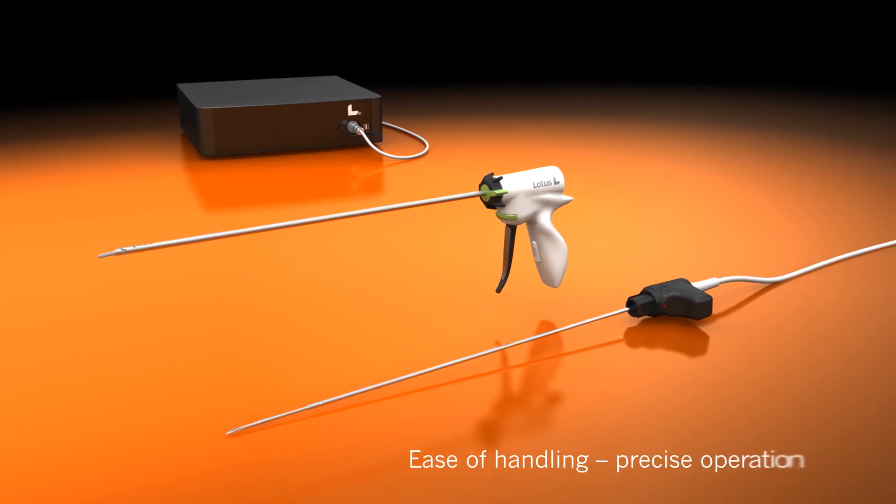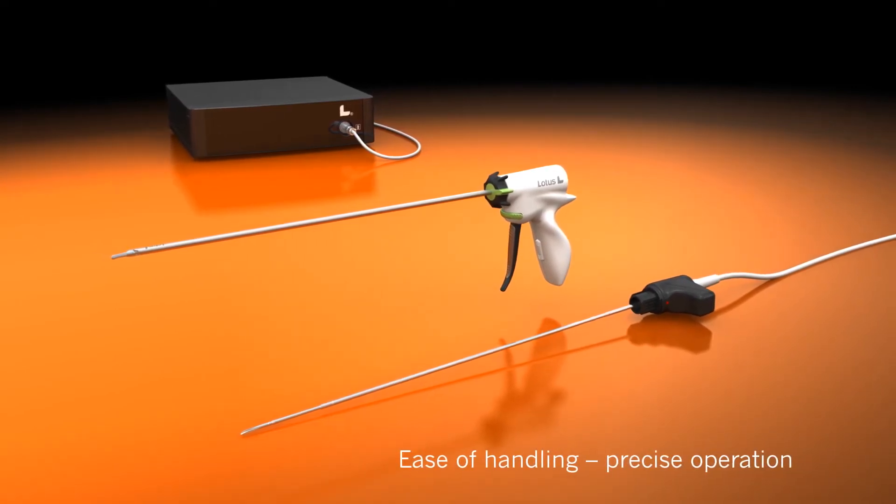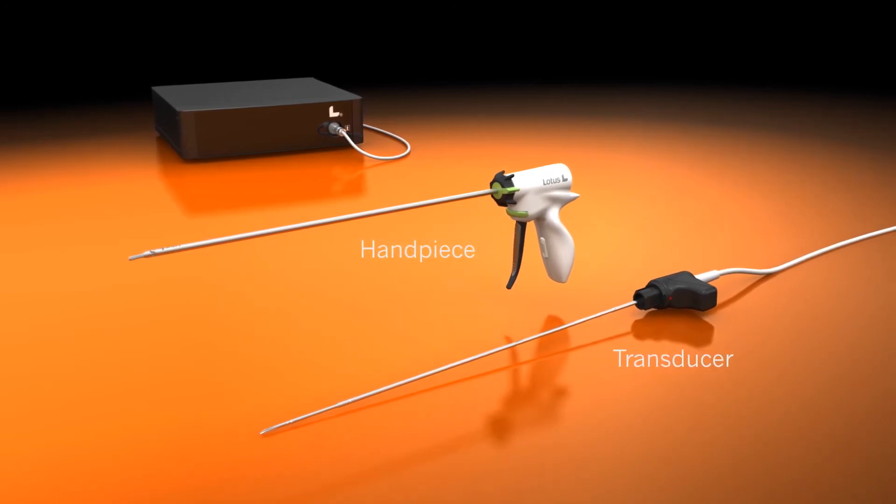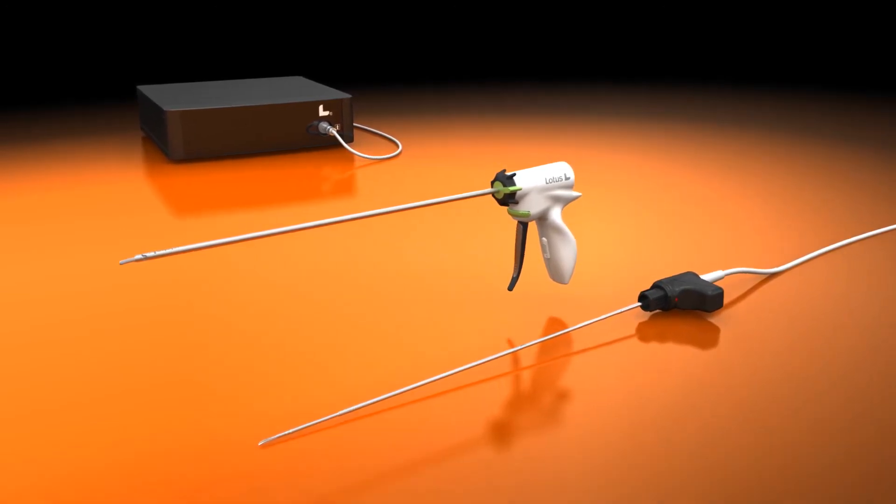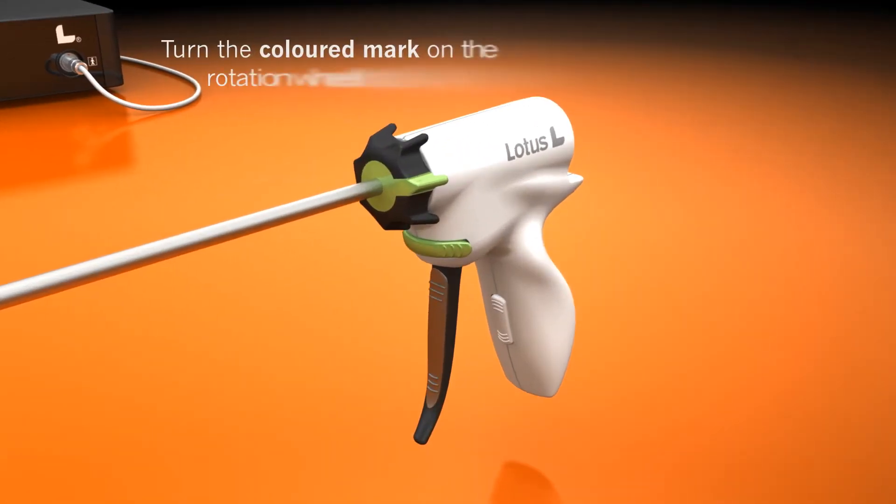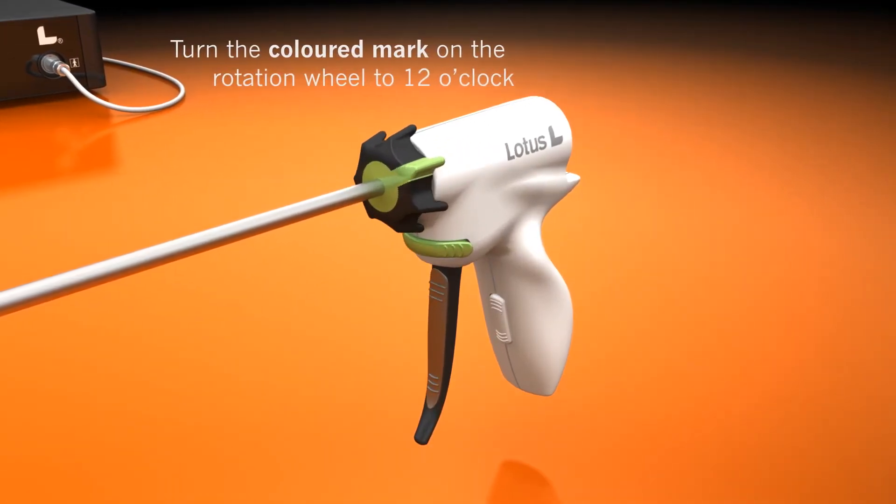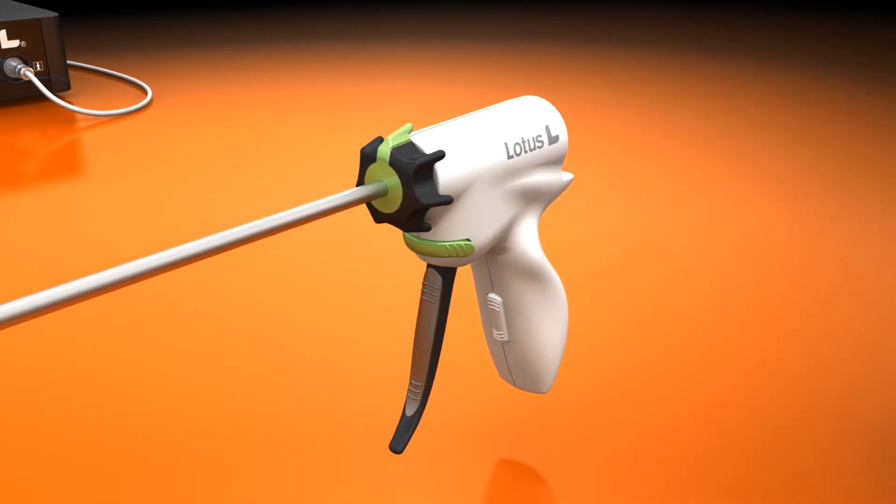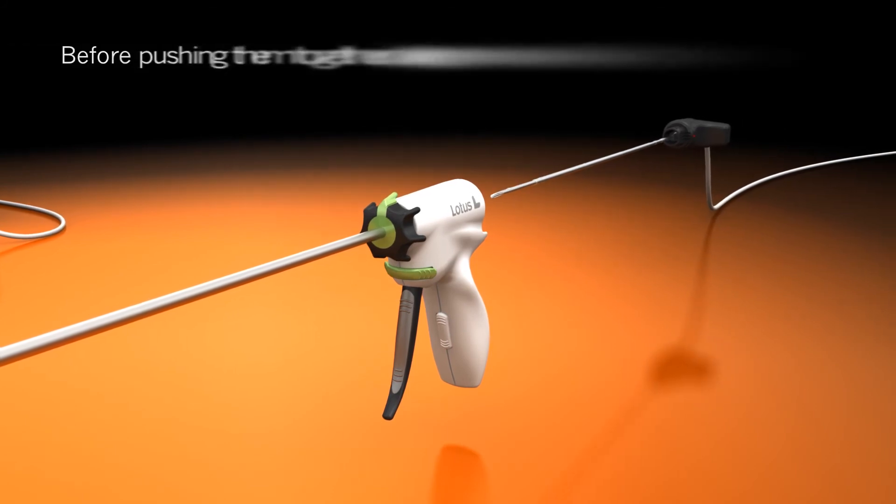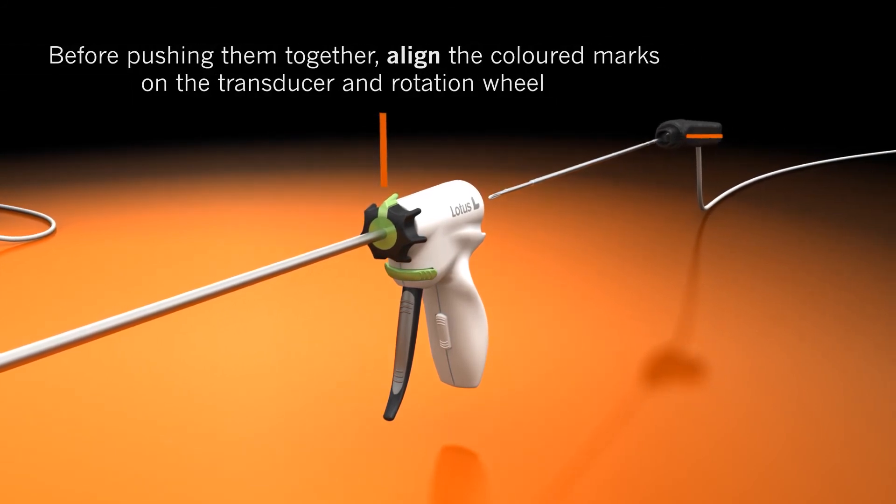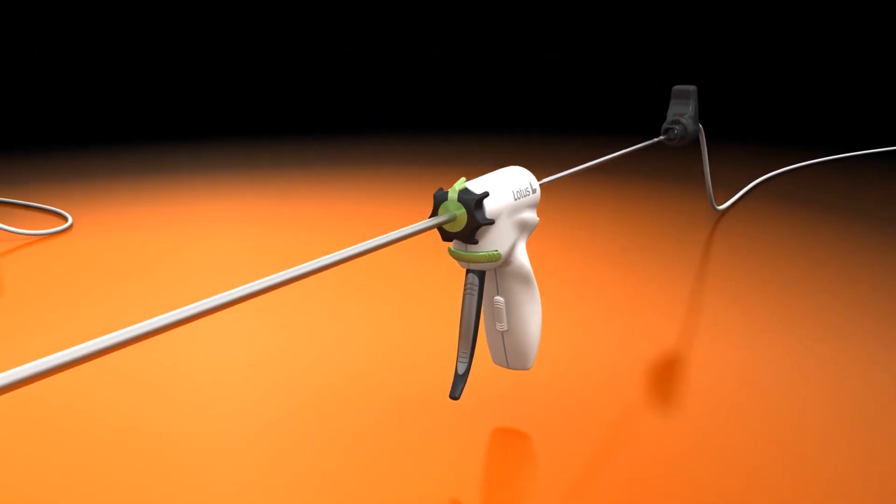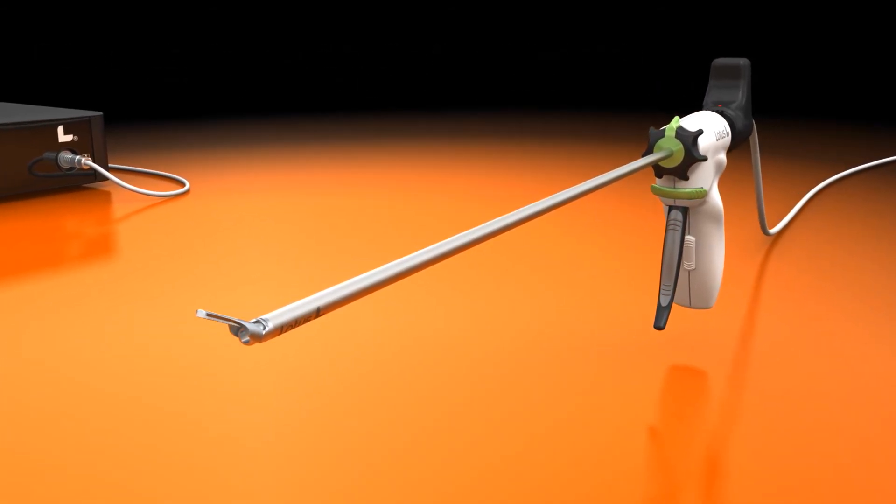The Lotus system stands out with its ease of handling allowing precise operating. The transducer is simply pushed onto the handpiece. Turn the coloured mark on the rotation wheel to 12 o'clock. Open the jaw of the handpiece. Ensure that the coloured marks on the transducer and rotation wheel are aligned. Push the transducer and handpiece together until the stop.